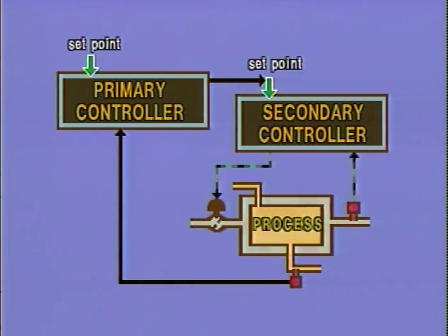The inner feedback loop is known as the secondary loop. In this loop, a variable, known as the secondary variable, is monitored and controlled just as in any basic feedback control system. The outer feedback loop is known as the primary loop, and in this loop, the primary variable is monitored. However, instead of directly affecting a final control element, the output of the primary controller is used to adjust the set point of the secondary controller.